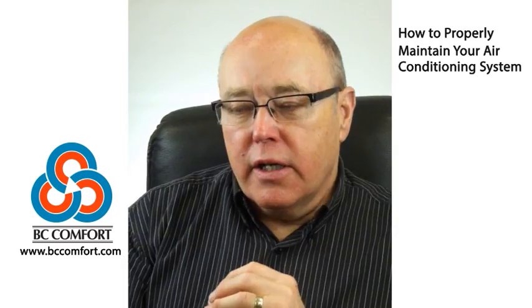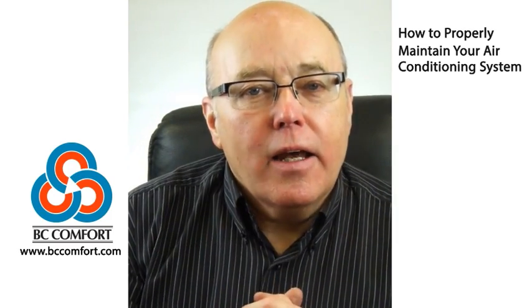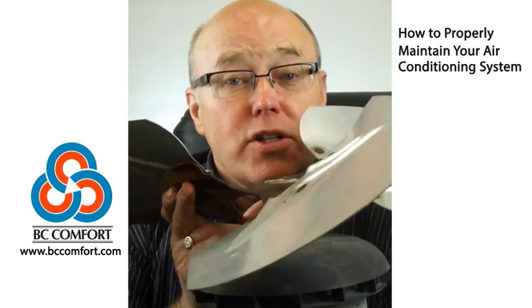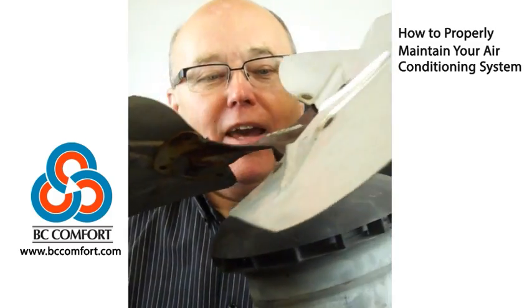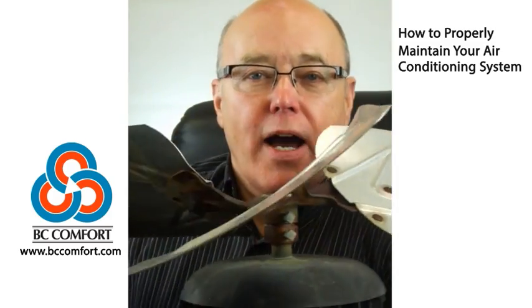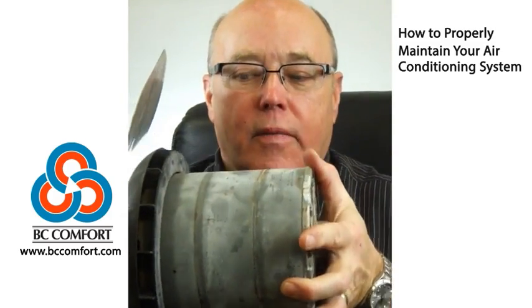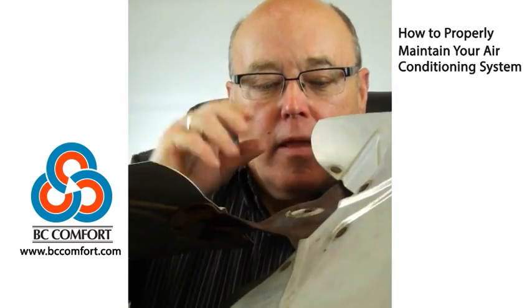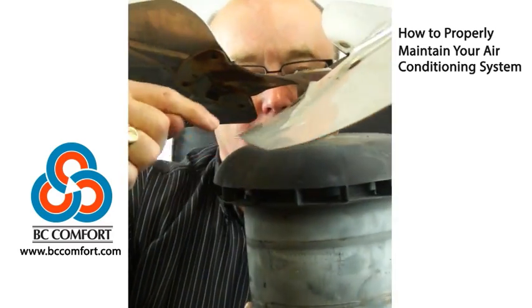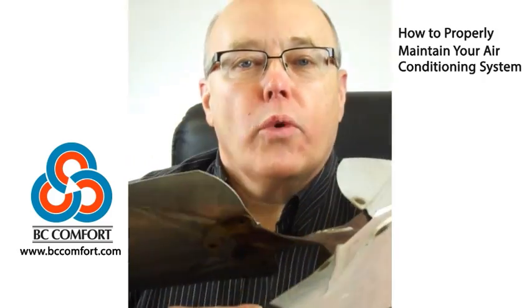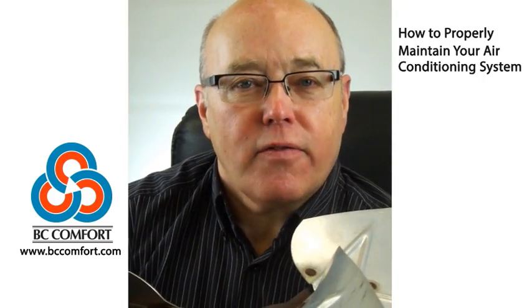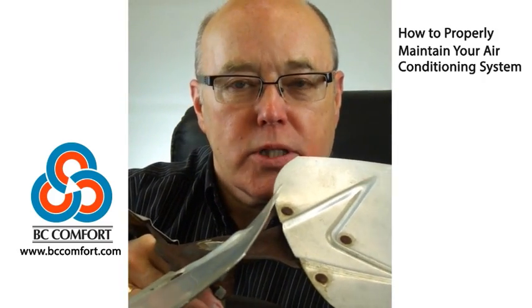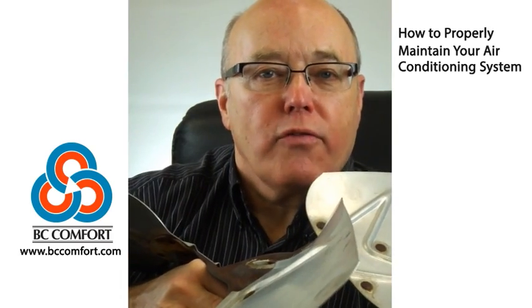What I want to show you here is a condenser fan. Again, a failure of maintenance. As you can see, it's obviously fairly heavy, right? This is a fan motor here and the fan blade. This part on top of the motor here is called the rain shield. This is to protect the fan because it sits in a vertical position like this, and this protects rain from getting into the windings of the fan.